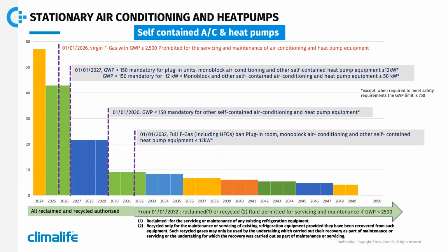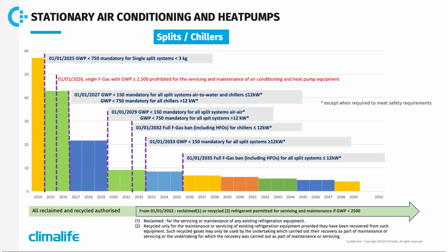Finally, on January 1st, 2032, all HFCs and HFOs will be banned for packaged units, standalone heat pumps, and heat pumps of less than 12 kilowatt. In the air conditioning segment with splits and chillers, on January 1st, 2025, refrigerants with a GWP of more than 750 are banned for single splits with a charge of less than 3 kg. There is still a ban on the use of virgin refrigerants with a GWP more than 2,500 for the maintenance of air conditioning installations, but this will apply from January 1st, 2026.